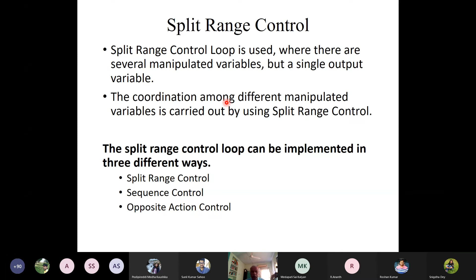If we look at the valves over here, we have 2 valves, valve A and valve B. For the split range control, the valves are tuned in such a way that, as the control signal pressure increases, which is nothing but an increase of the controller output, initially valve A is fully open and valve B is fully closed. As the controller output increases, valve A's opening decreases, and at the midpoint, or 50% of the controller output, valve A fully closes and valve B opens. This is basically called the split range.